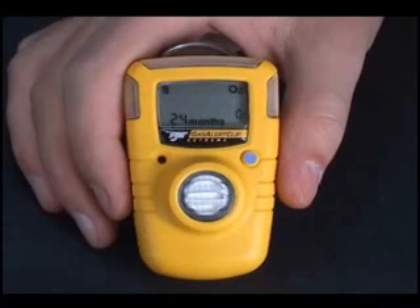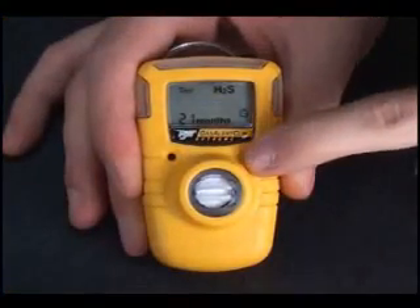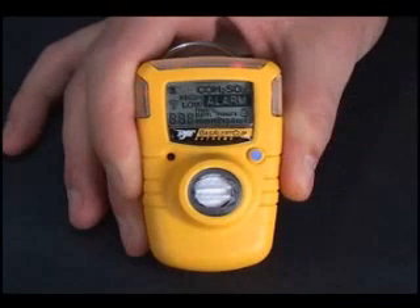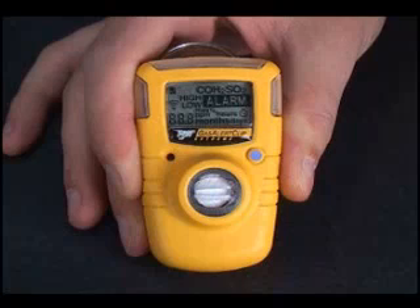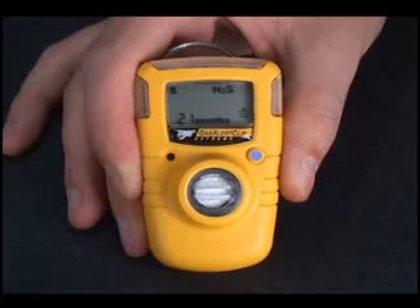Gas Alert Clip reminds you to run a daily self-test. After 24 hours, the check mark will disappear and the display will read 'Test.' In a clean atmosphere, free of background gases, press the button. The word 'Test' flashes. The test verifies sensor, circuitry, and battery integrity. All display segments light. The visual and audible alarms activate and the alarm set points are displayed. A check mark appears to confirm the Gas Alert Clip has passed all tests.